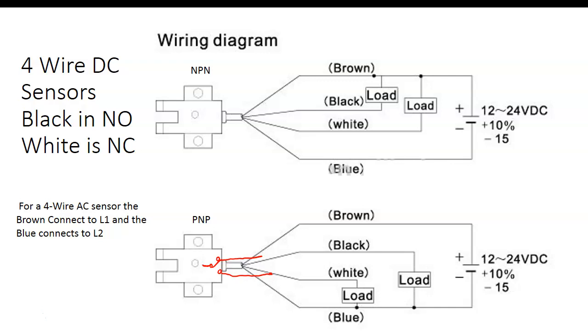So ground would go back towards the what? It would go back to the minus. Now notice here, what would this be? This sensor would be a sourcing sensor, right? Because the loads are connected to minus. This would be a sinking sensor because your load's common is connected to plus.